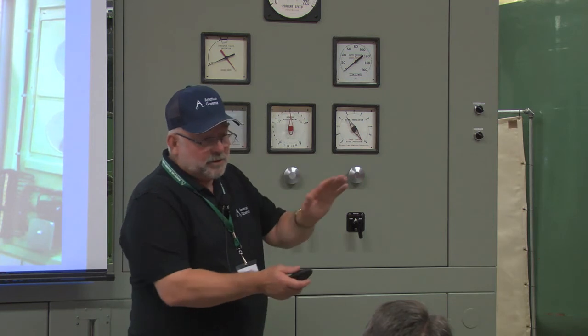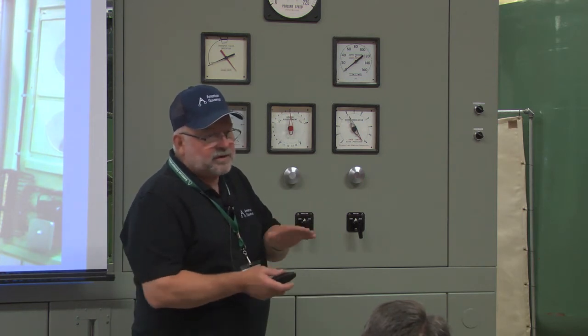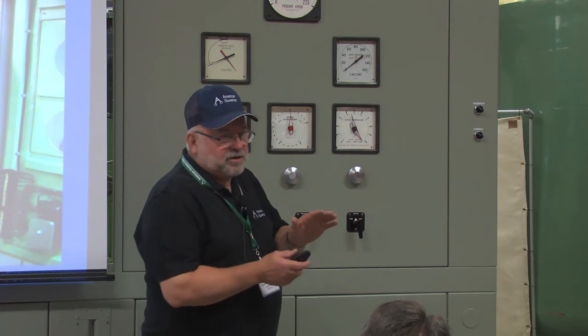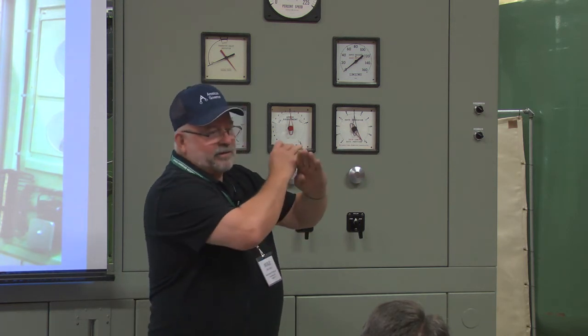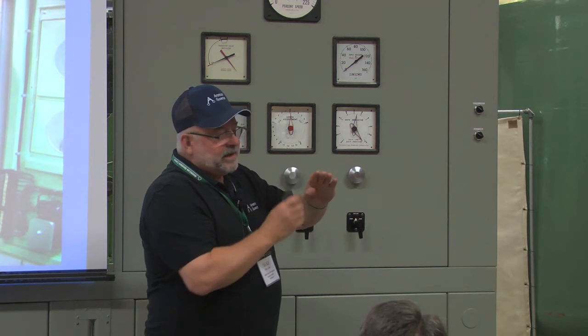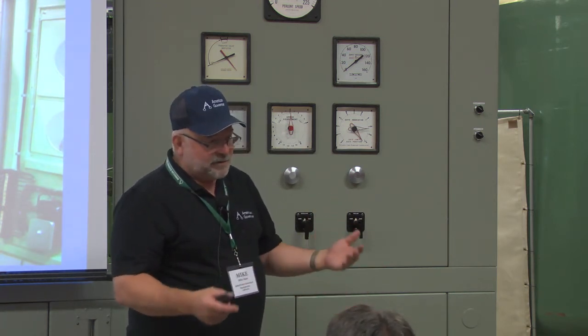Really? Okay. We always did it at 5%. All right. All that means is, and that's USBR, that's what they do. The Corps does the same thing. And all that does is change, you know how you saw the droop curve in the class? Instead of pivoting at 50%, it pivots at 10%, speed no load. Now, the reason they do that makes good sense to me. The only thing that counts is from there up, is what they're saying. But all it does is it doesn't make a few things linear. The unit still works fine. It still does its thing.